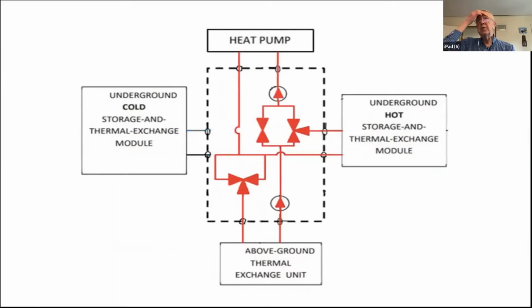Now, if we want to, we can do what's called a parallel mode, and that's what this is. If you have a temperature from the above ground unit, which is very similar to the temperature from one of the units below ground, you can have part of the water coming from both of them. And to keep it simple, you might have the same water flow from both the bottom unit and the right-hand unit. To do that, all you have to do here is control the top water pump to have twice the flow rate of the bottom water pump. And in that case, the same amount of flow will be coming from both blocks, the right-hand one and the left-hand one.